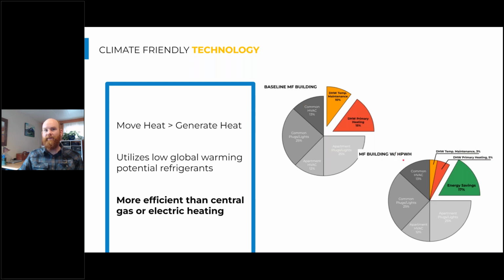Our commercial multifamily buildings are a little bit different than single family homes, where we typically don't have that temperature maintenance system in the single family home application. We often don't have a circulation pump unless it's a rather large home or with bathroom groups on opposite sides of that home. In a commercial multifamily building, this is a big aspect of the system, and we can see that it's a lot of energy that we're throwing out by essentially cycling that water through the piping to keep it at temperature. That consumes a lot of energy on an annual basis.